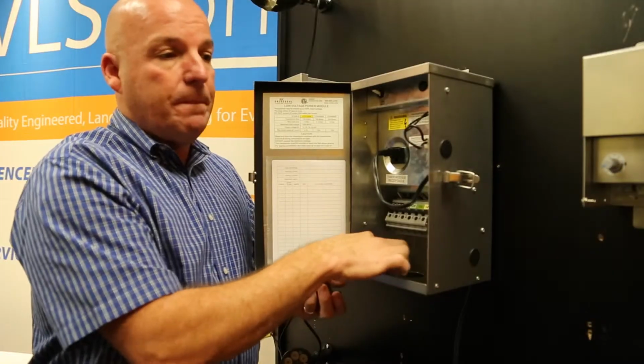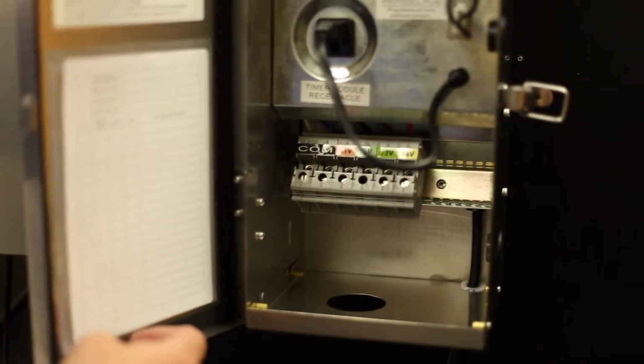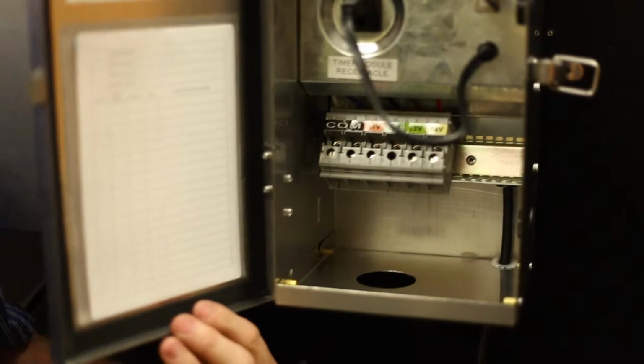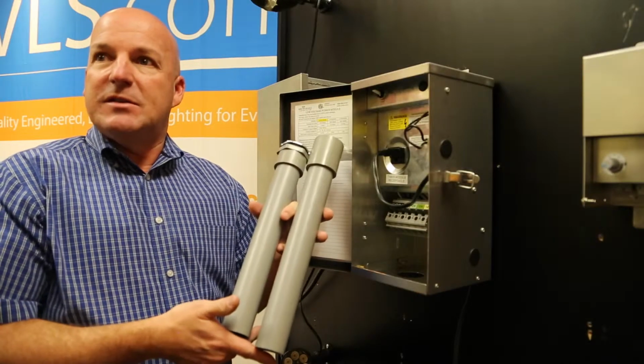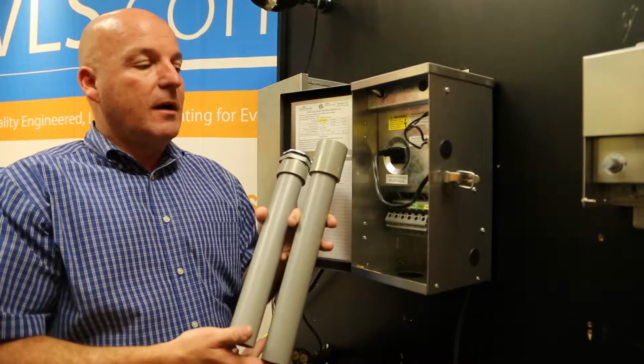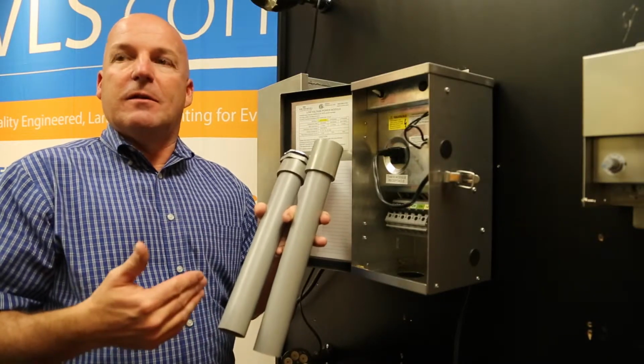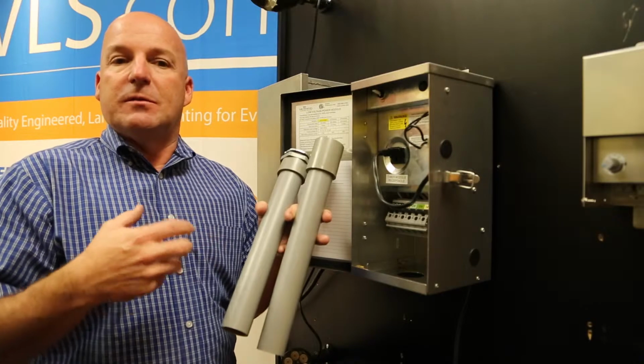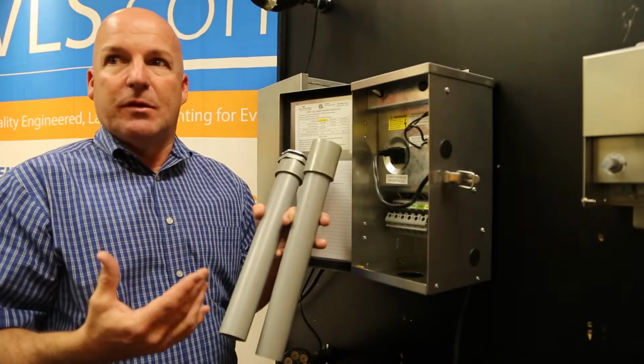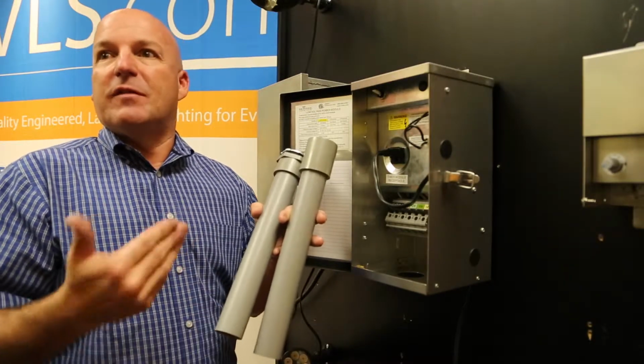The other thing we did: you'll notice on this panel there's only one hole, an 1 1/4 inch hole. With each of these transformers, we ship 2 12-inch pieces of 1 1/4 inch conduit. Unlike a lot of people out there, your distributors or dealers may not have the conduit available for you, but you want a nice, clean, professional installation.